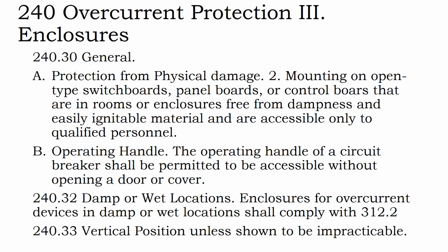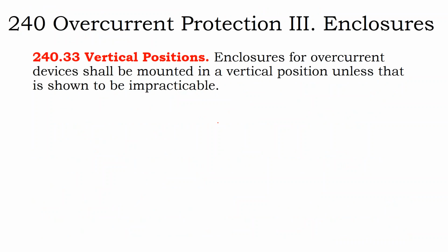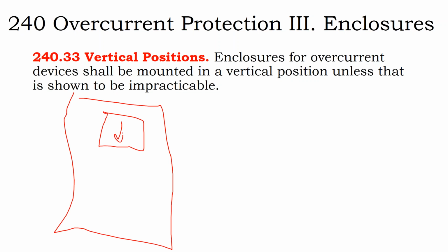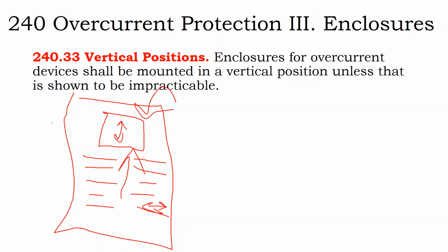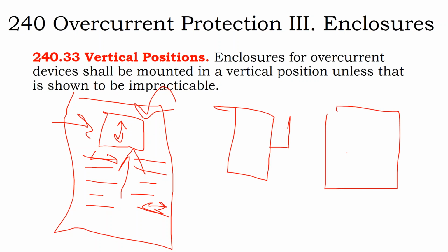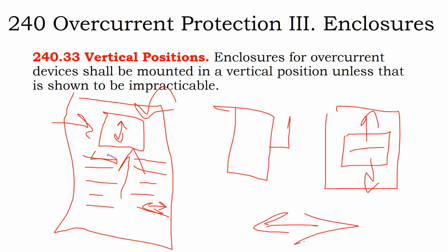Let's see. So we've covered a lot of these positionings. Enclosures for overcurrent devices shall be mounted in a vertical position unless impracticable. And so, if you have a service panel with a main overcurrent device, it's more important for that to be up and down than your side-mounted breakers plugging into that device. So your side-mounted breakers are allowed to be left and right because it's impracticable in your service panel design to have a main that's up and down and side breakers that are also up and down. But if it's the choice of, if you have a knife switch with a handle on it, or even just a single service panel with a single breaker switch on it, it should be mounted so that that breaker is going up and down rather than left to right as a standard layout.